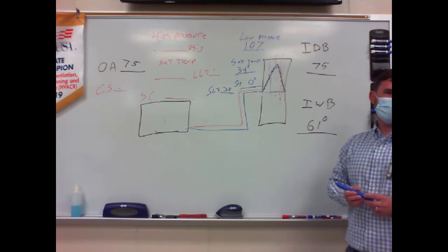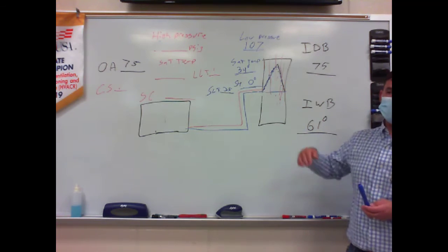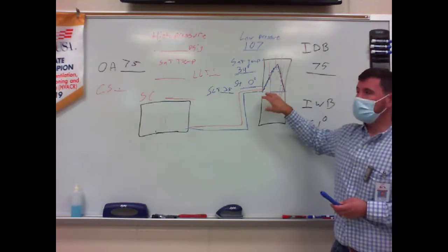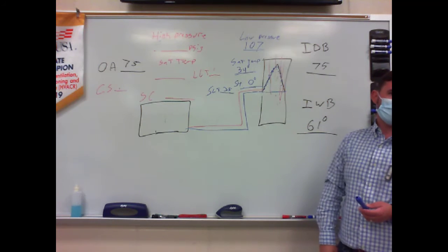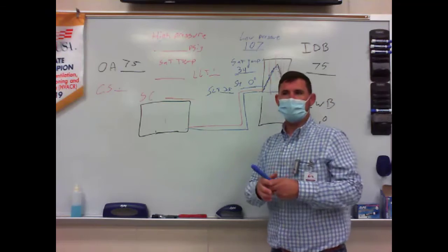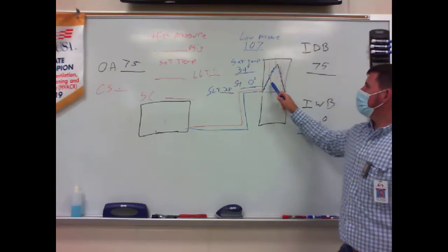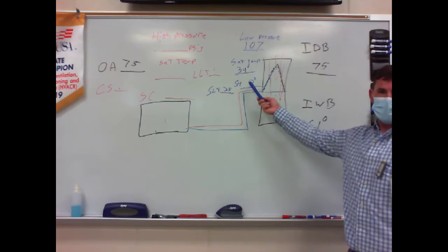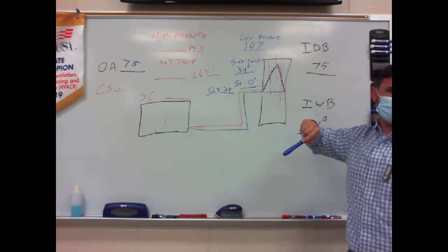No, say it again. You said with it being a piston, should it be a higher superheat? Yes, your superheat is going to vary depending on what your head pressure is and what the heat load is on that coil. So using my chart, and I have slide rules and different things that all tell me the same thing, what my superheat should be under given conditions. Using that, I should have 15 degree superheat, but I have 0 degrees. That means I'm not picking up enough heat, or I have too much refrigerant in there.